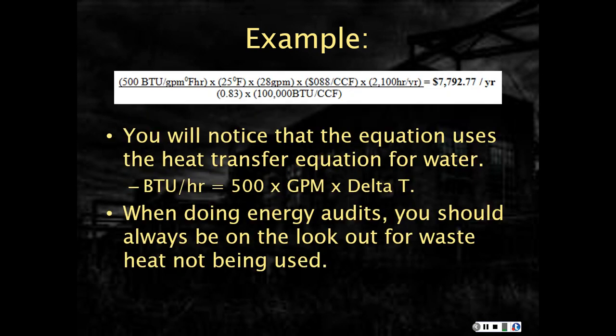So if we put those values into the formula, we have the 500, which is a given for water, times the temperature rise, times the flow rate of the water in the process, times our energy cost, times the hours per year that the process runs, divided by the efficiency, divided by the fuel BTU content, and we get $7,792.77 per year.